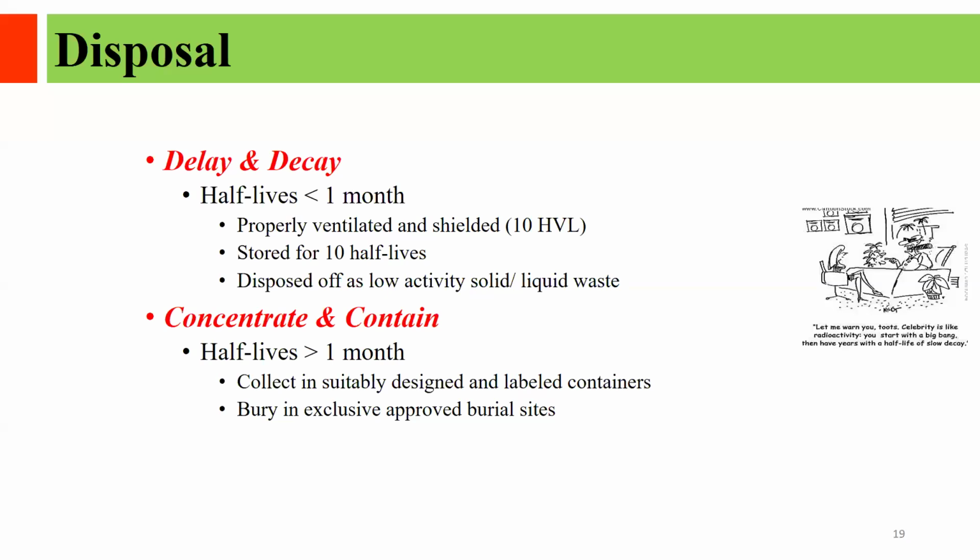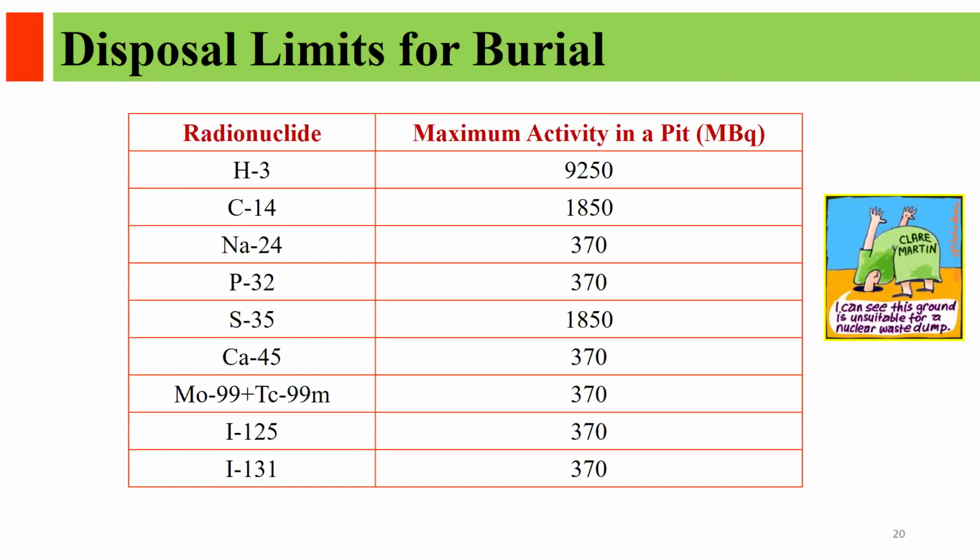When we call it concentrate and contain, if the half-life is more than 1 month, then it has to be suitably designed with a labeled container and kept, and then you have to bury it in exclusively approved burial sites, which is generally maintained in our country by the waste management agencies. These are the certain disposal limits for burial which are followed for tritium, carbon, sodium, phosphorus, sulfur 35, calcium, molybdenum, technetium, and iodine 125 and 131. This is the activity which can be buried in a pit.